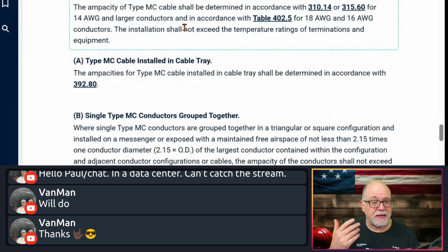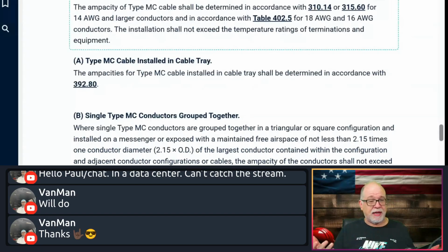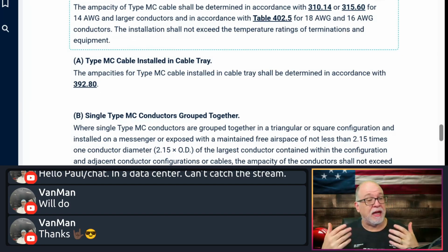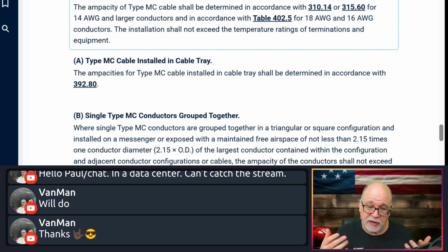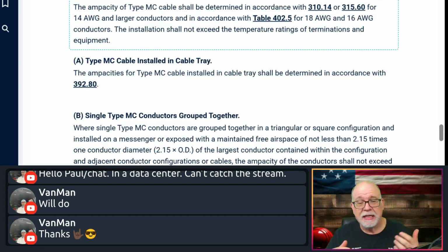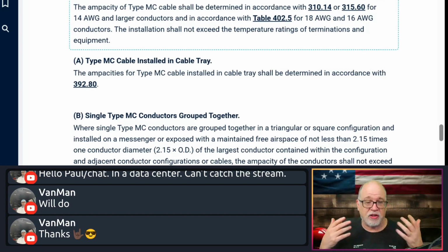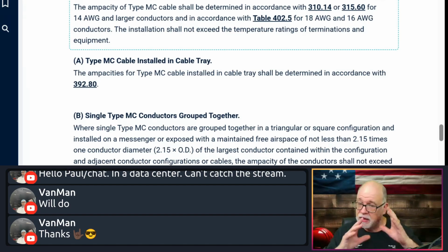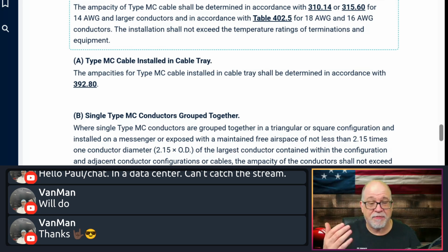So for me and you, typically the ampacity is 310.16, but we do have adjustment and correction applications. And you will see that there is a benefit for MC cable and bundling. If you look at 310.15(C)(1), you will see that there are some allowances up to a certain number of current carrying conductors in a bundle where, even after adjustment and corrections, you're still fine. They have some allowances for bundling in those applications. But again, be aware of that. It can affect your ampacity.